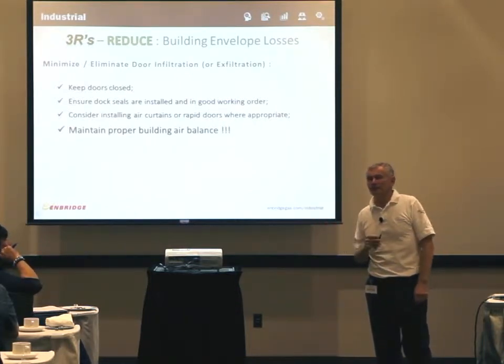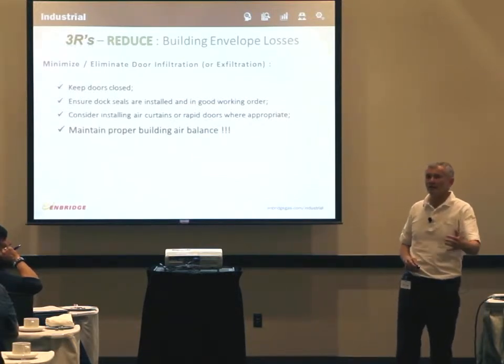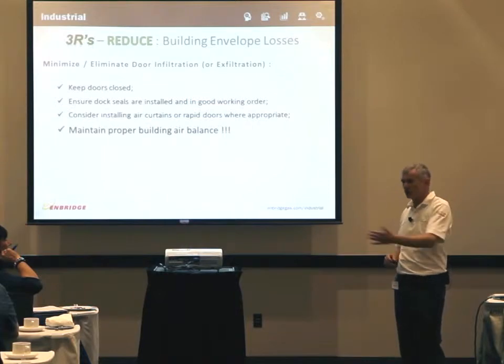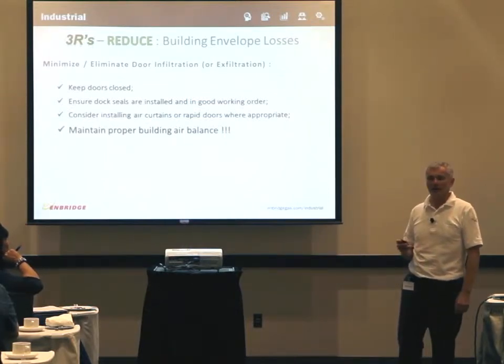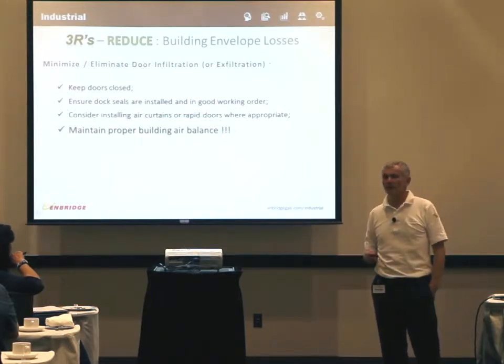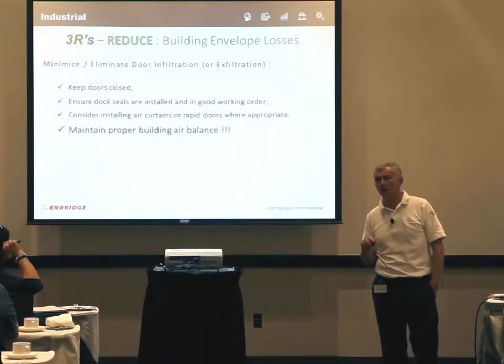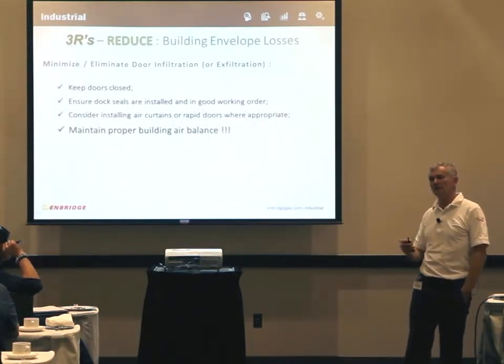What does infrared do? Infrared heats the floor, right? So if you have 500 cubic feet of air rushing by that infrared, you really think it's going to heat it up? No, it won't. It won't make any difference. It will have a nice red bar above the door. It won't make any difference to the quality of the indoor air or the drafty environment that people see downstream.